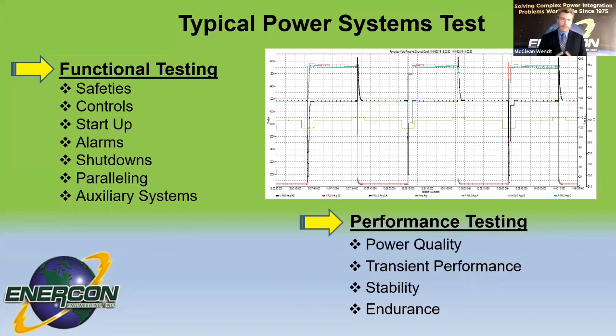And we've done all sorts of durations, whether it's 4 hours, 24 hours. We have a large project that we typically run for a week straight, 24/7. And then there was a picture earlier of tests that we did for 30 days straight on 2 units with 4 generators between the 2 of them. So those will help prove the resilience of a system.